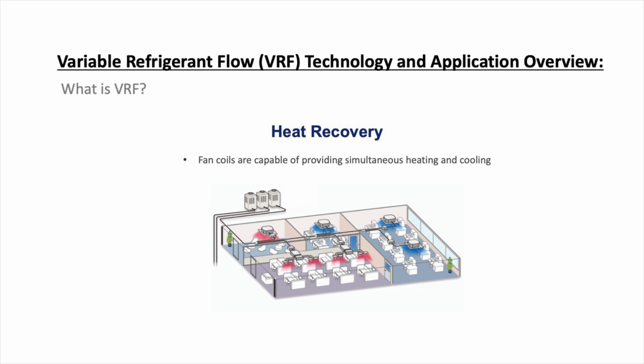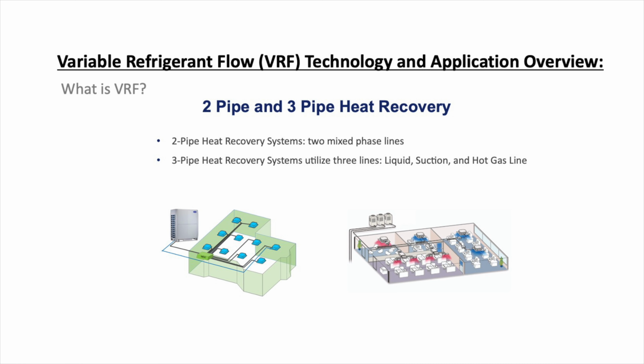With heat recovery, fan coils are capable of providing simultaneous heating and cooling. So if you have one zone that calls for heating and another zone calling for cooling, both of those zones can be satisfied at the same time by the same outdoor unit. And there are two different types of heat recovery. You have 2-pipe and you have 3-pipe.